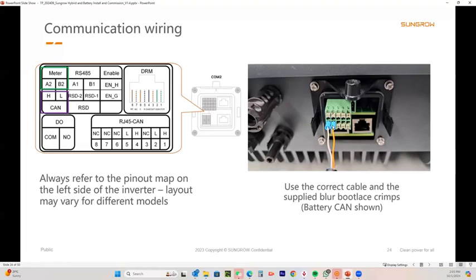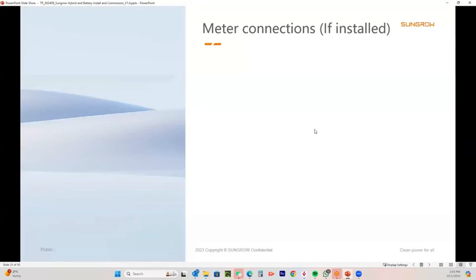And you'll see there's blue crimps. These are the crimps that we supply in the box, and they're longer than the standard size. They have to be, because you push them in to the terminal to get the connection. If you don't use these, you will almost certainly get a bad connection, and you'll get data dropouts and stuff like that. And the last thing you want to do is have to go back out onto site just to remake one of these ends. So you just crimp them and they push in. If you need to take them back out again, there's a little white block there with the spring. You just push that in and you can take these back out. So the meter would be going into 1 and 3, and the battery into 2 and 4 there.